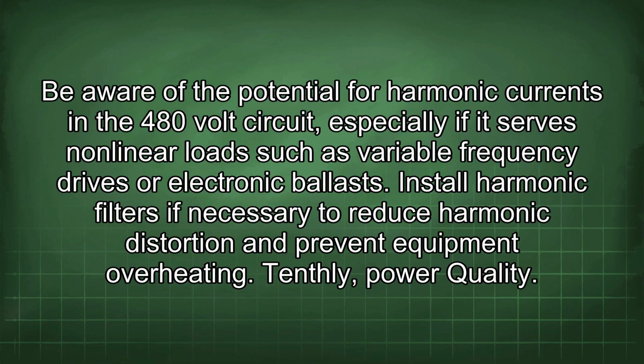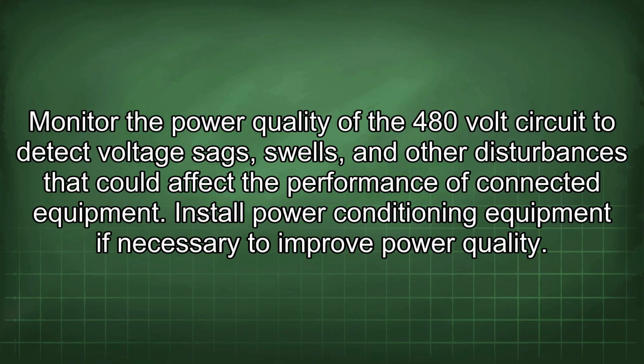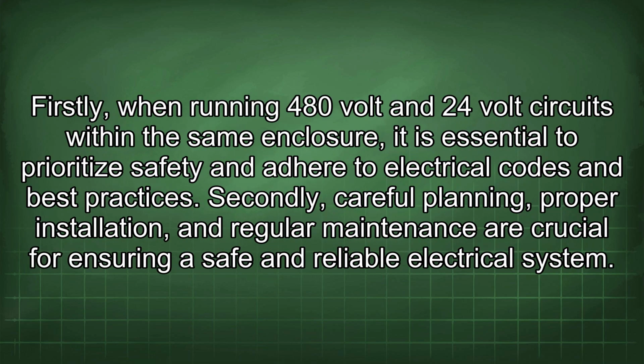Tenthly, power quality. Monitor the power quality of the 480-volt circuit to detect voltage sags, swells, and other disturbances that could affect the performance of connected equipment. Install power conditioning equipment if necessary to improve power quality. Firstly, when running 480-volt and 24-volt circuits within the same enclosure, it is essential to prioritize safety and adhere to electrical codes and best practices.